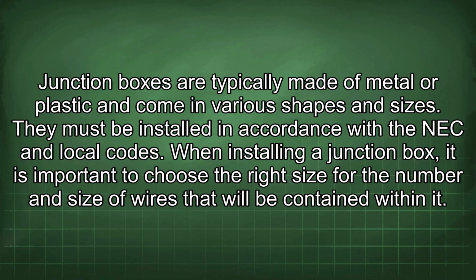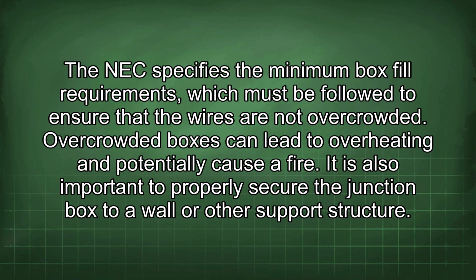When installing a junction box, it is important to choose the right size for the number and size of wires that will be contained within it. The NEC specifies the minimum box fill requirements, which must be followed to ensure that the wires are not overcrowded. Overcrowded boxes can lead to overheating and potentially cause a fire.